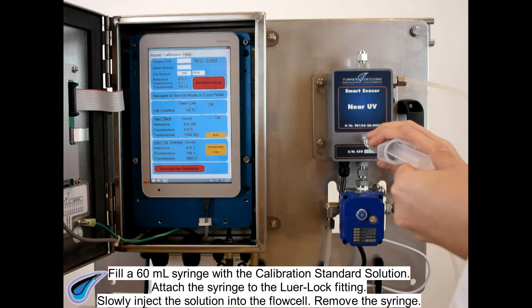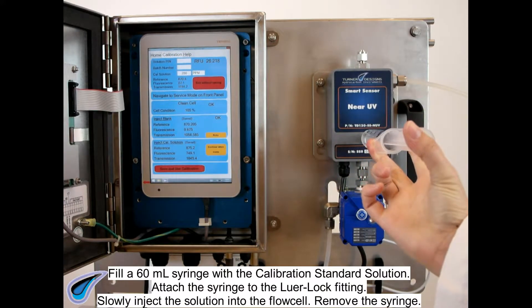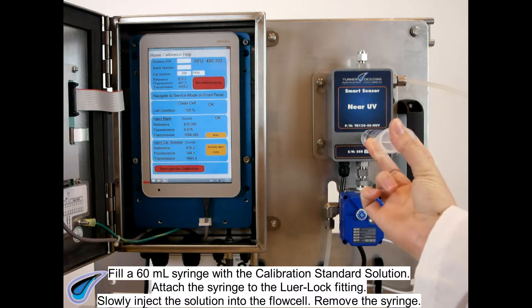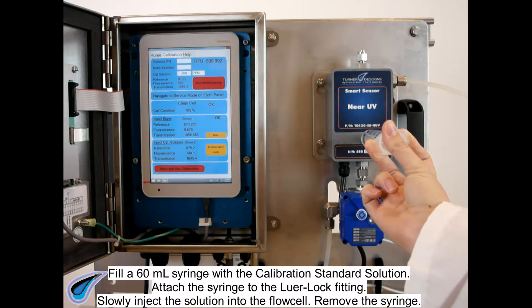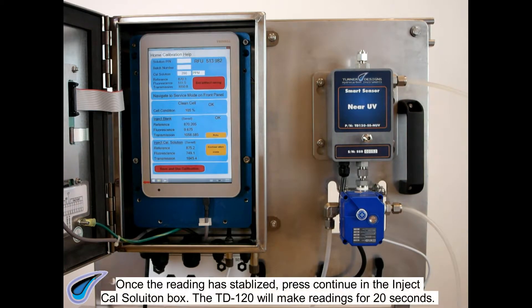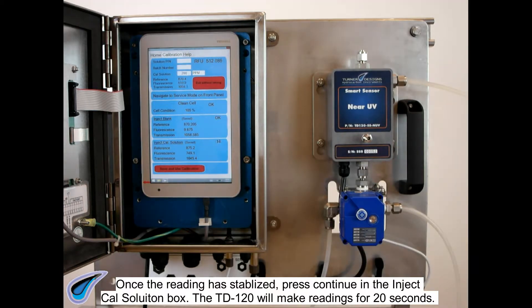Fill a 60 milliliter syringe with the calibration standard solution. Attach the syringe to the Luer-Lock fitting and slowly inject the solution into the flow cell. Remove the syringe. Once the reading has stabilized, press Continue in the Inject Cal Solution box.